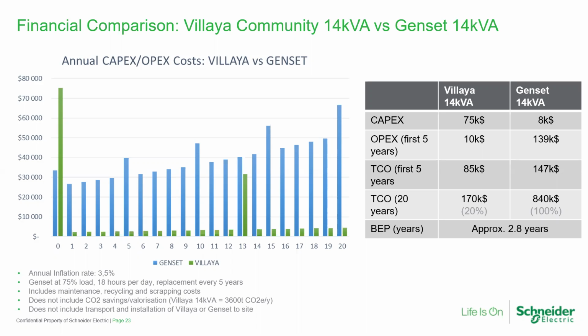So you can see the Villaya in year 0, in green, with a very high capex cost of around $75,000 US, compared to the genset capex of $8,000. But once you factor in fuel costs for year 1, the genset is already up at over $30,000. After the first 5 years, the Villaya's OPEX is around $10,000 US, since we're only dealing with basic maintenance, whereas the genset involves maintenance plus fuel consumption, burning around $140,000 worth of fuel in the first 5 years.